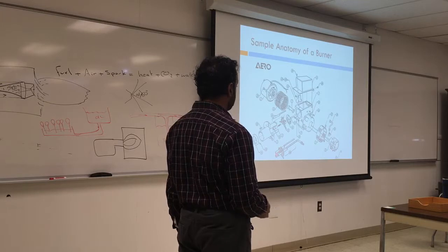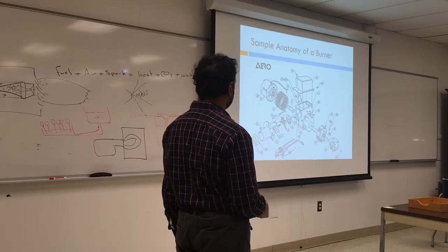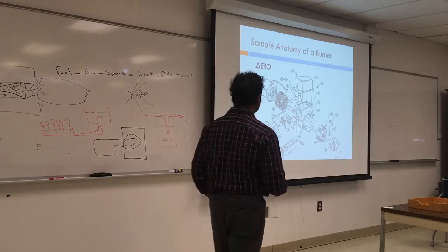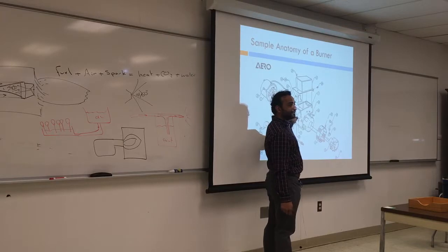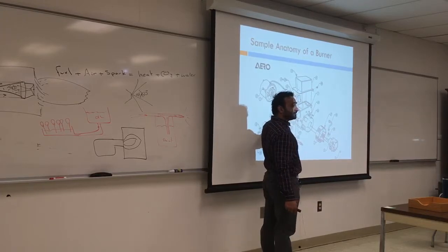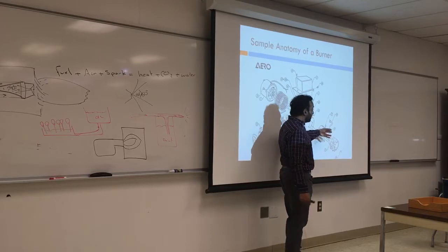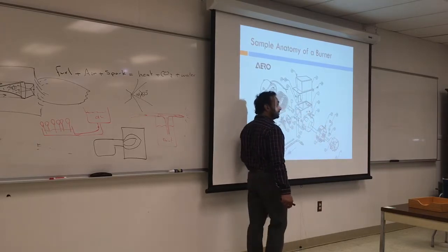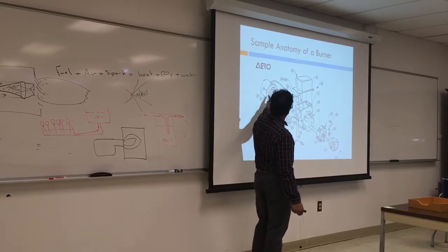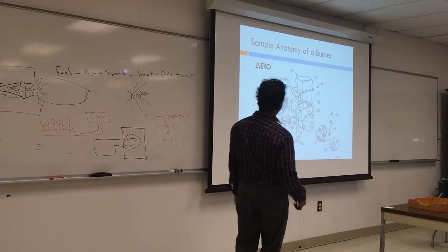Electrodes. These are electrodes, and this is the nozzle assembly. The nozzle goes in here. What about this one? That's the diffuser. It holds the nozzle assembly in place. What about this one? That's the coupling. That connects the motor to the pump. What about this? Squirrel cage fan. This fan will create pressure to bring in air from the outside through the air band all the way to the nozzle compartment. Motor, transformer, and these are the main components you're gonna have for the combustion.